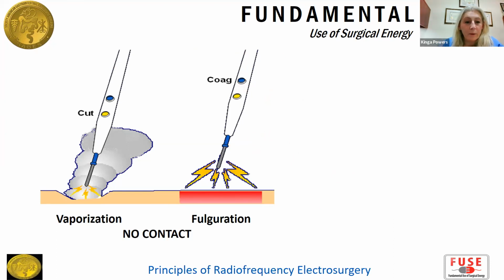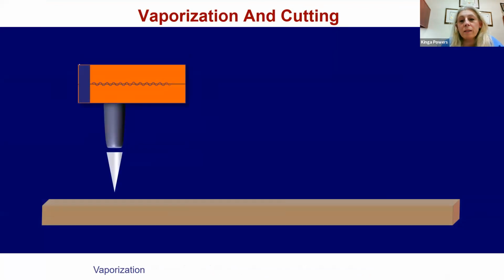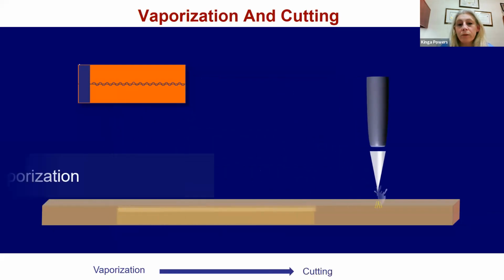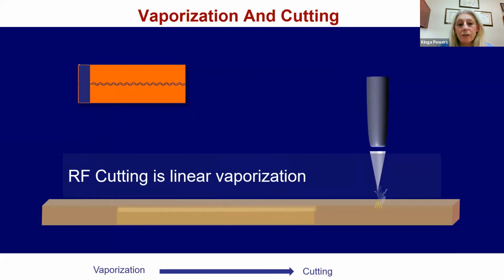I'll talk about that a bit more. The cut mode has the lowest voltage. Like we said, you have that continuous, spread-out thin current, continuous for the set power. It's designed to divide tissues with the highest concentration of heat but very little collateral damage, so very little coagulation or desiccation of tissue. This mode uses a low voltage waveform and produces maximum current concentration.